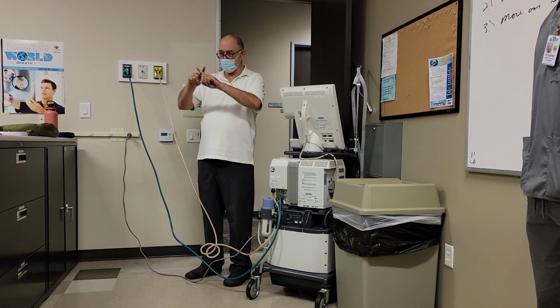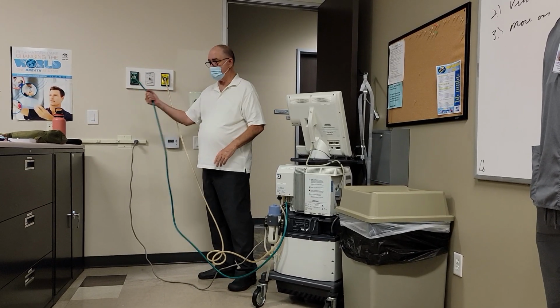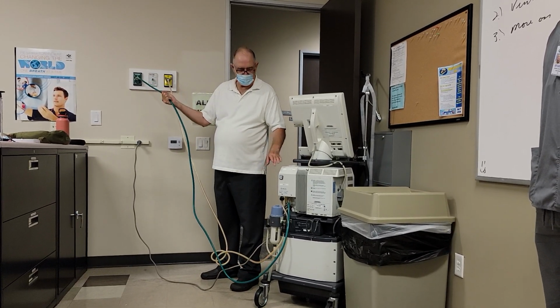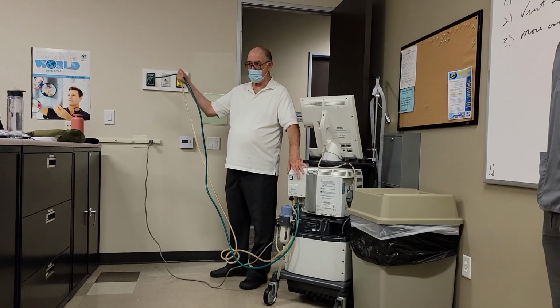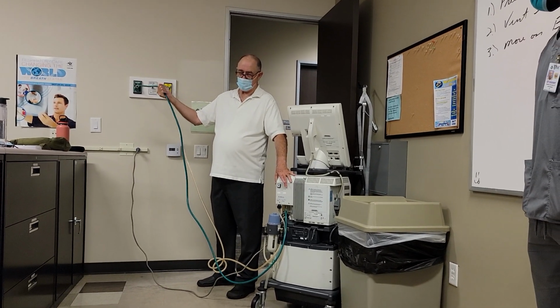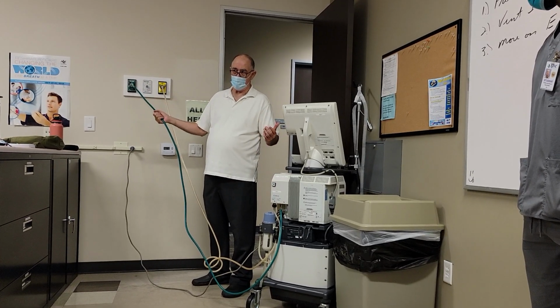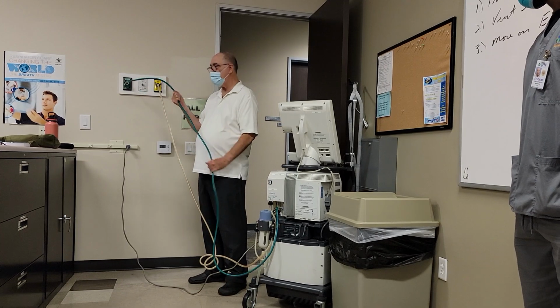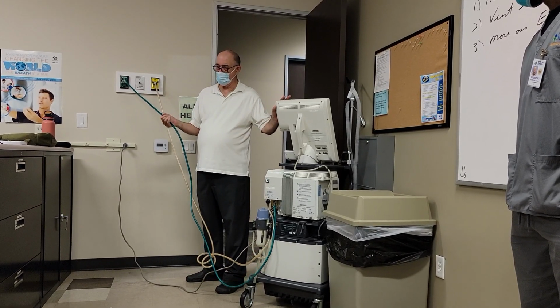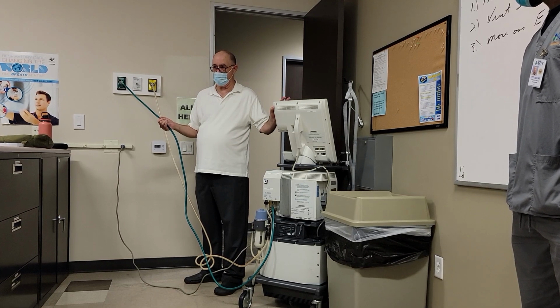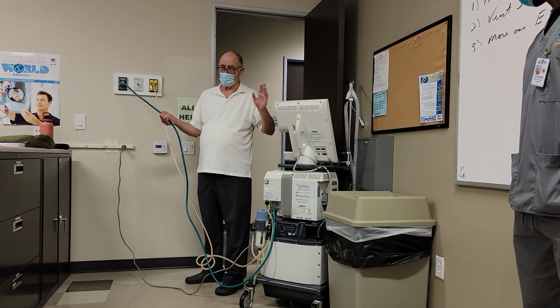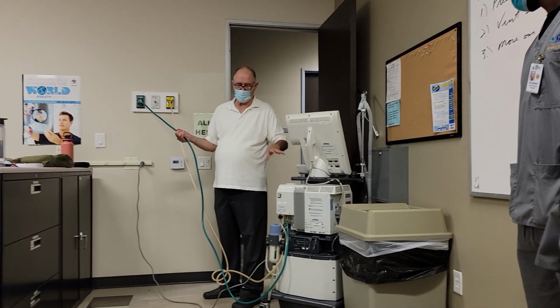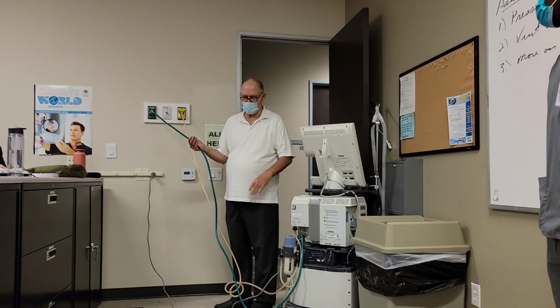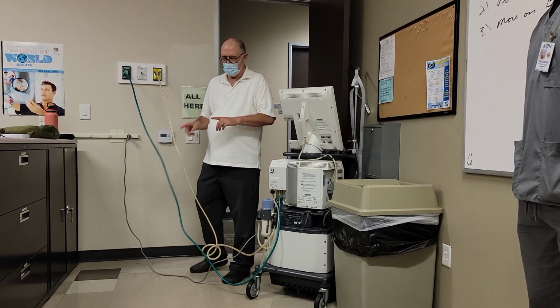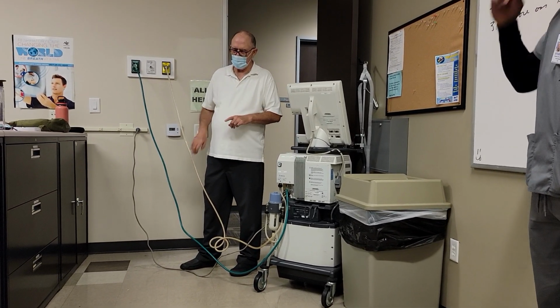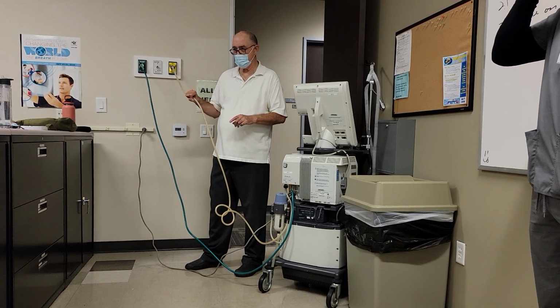And it has what's called a crossover valve. If my oxygen goes bad, the sensor in here will pick up the fact that I'm using room air where I don't have oxygen, and it will alarm, okay? So since all we have is air, we'll only do this on 21%. In fact, some of the ventilators are still gonna alarm because they don't see oxygen because of the analyzer, so we just ignore that. But if it loses pressure, it will still operate off of the other one. So that's a safety element.